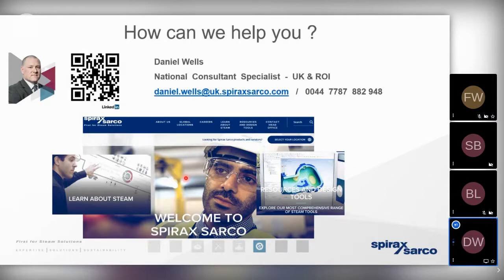Difficult question to answer. If you can imagine a hospital, a tower block hospital. If we've got a plant room on the 10th floor, then the condensate as a liquid could potentially return back to the boiler house under gravity. However, if we've got a distribution network that is quite vast, spread out horizontally, for example, then it may well be, if we're condensing the steam at a low pressure, let's say at 1 bar gauge, 120 degrees, then there isn't going to be enough motive energy in the upstream of the steam trap to push the condensate a considerable distance. Under circumstances such as that, we may need to add some motive energy.